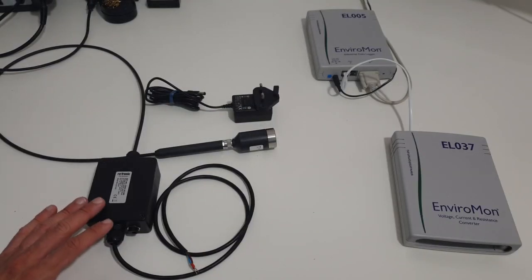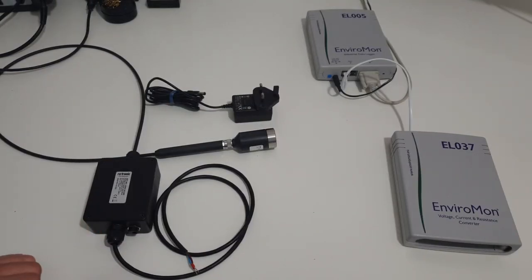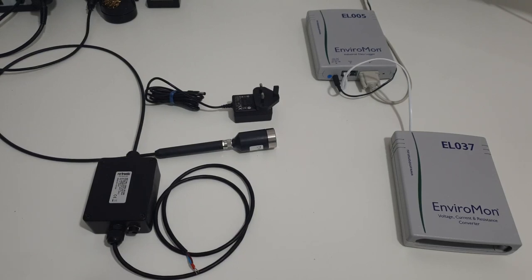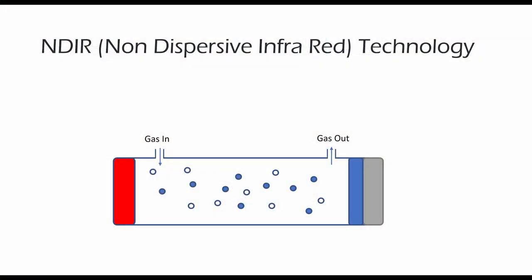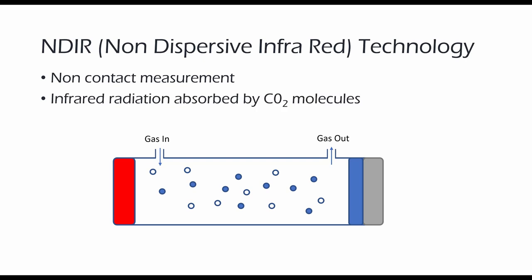So we have today the Rotronic CO2 probe which we sourced for customers who want to measure the CO2 levels in an egg incubator in their factory. So this is an analog probe using non-dispersive infrared technology or NDIR for short, which is used to measure carbon dioxide for incubators. NDIR sensors are an efficient and reliable method of measuring gases as they have no contact with the gas.